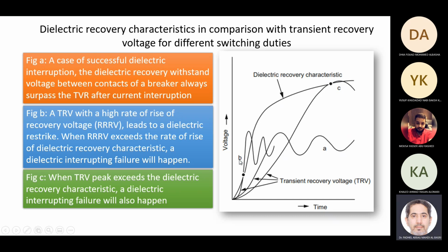However, like in case B, initially the voltage that will develop is lower than the insulation media recovery, so it will quench the current. But at this point the voltage across the contacts is higher than the insulation dielectric strength. So as a result, it will break again. The arc will reignite again, and the current will not stop.